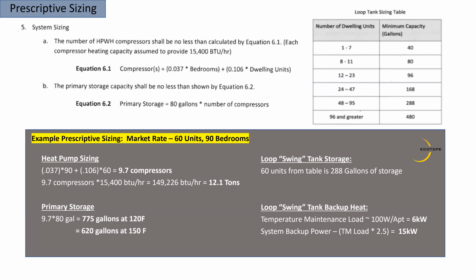This is an example of some of the sizing. Using the prescriptive California sizer, I ran a 60 unit, 90 bedroom market rate sizer. We can see it comes out to about 12 tons. You do the math following this equation on the storage, it's 80 gallons per 9.7 compressors. The compressors in this case would be the Sanden water heaters. The Sanden water heaters have the most research on them. They're kind of the furthest ahead in the technology innovation model. They've been out in the market for around 8 to 10 years.